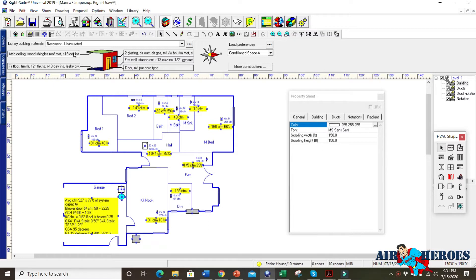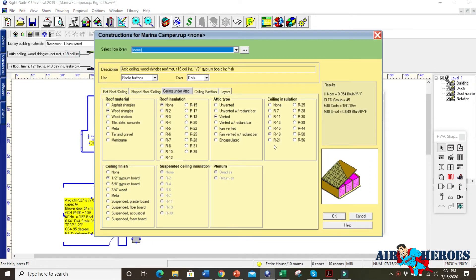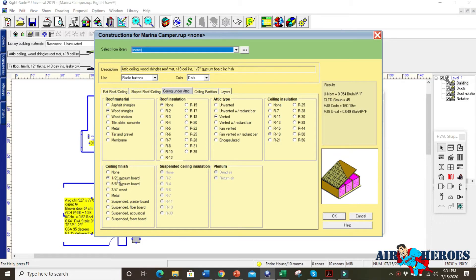So the first thing we do is we got to measure the house. So we measure the house and then we do what we call a test in to check everything because she doesn't need her unit replaced. She just needs a lot of extra work done. So first off, let's just go over the house itself. It has R19 in the ceiling. Wood shakes, half inch gypsum board at the ceiling.